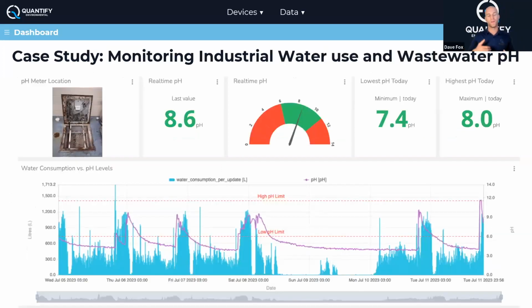So now we can take water, which we see here on the base graph, but then we can start layering on top of that other sensors we've installed. This particular facility had an issue with their wastewater pH. In the top left, you can see the exact wastewater pit we're talking about. We put our pH sensor in there, minute by minute, real time, alerting production staff and management when they're over or under pH, because that results in significant fines. They can avoid that and keep track of their baseline flows and production sanitation water use.